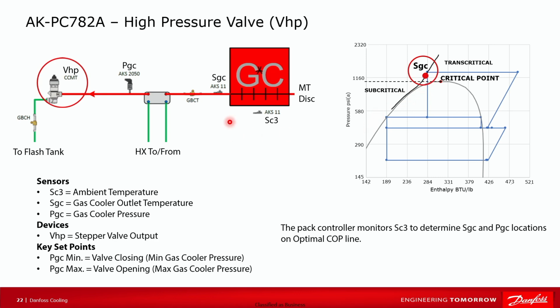What the valve actually cares about is where the gas cooler outlet temperature is in relation to this line. What that line actually is, I think I've got coming up on the next slide. My apologies, I got ahead of myself. So the valve is going to open and close to keep this sensor on this COP line here. Let's assume I were over here with the actual sensor reading. The high pressure valve will lower the pressure to bring it back onto that line.